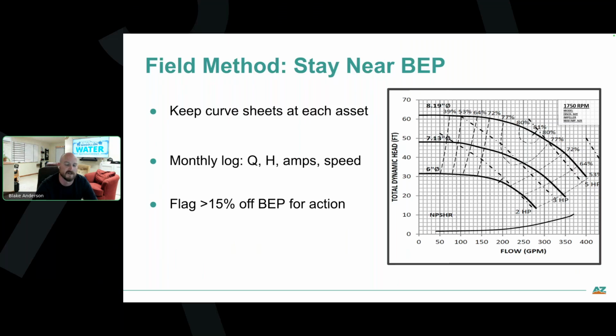Do you have a difference in system pressure that you're pushing against? Is there a valve restriction? Did you change something with the speed? Are your pumping levels changing, or is the motor just rolling out?